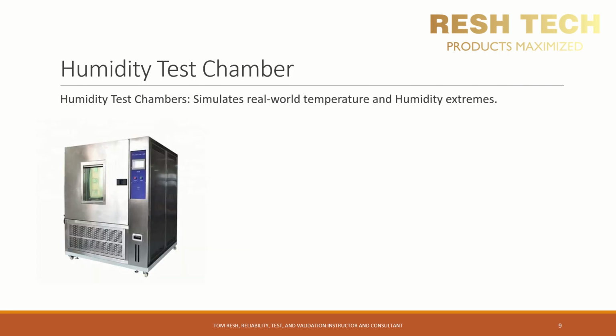In the magical world of humidity testing, the go-to test equipment used is a humidity test chamber, or temperature humidity chamber. As pictured, the outside of a temperature humidity chamber looks a lot like the run-of-the-mill temperature chamber. However, there are a few internal components that are added to a temperature chamber to produce high and low humidity environments inside of the chamber.